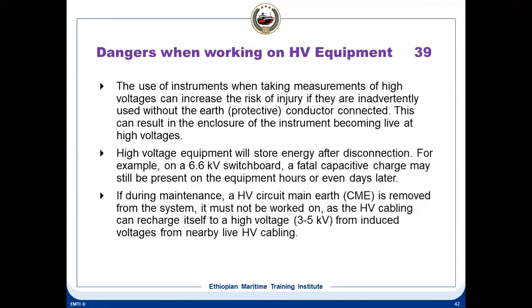The use of instruments when taking measurements of high voltage can increase the risk of injury when they are inadvertently used without an earth conductor. You see, the first thing in a high voltage system is grounding. Everything has to be grounded before you touch anything. The whole purpose of grounding is that any residual voltage has to be discharged to the ground or earth. That's the first part. Whether you use a megger or test the voltage or whatever it may be, grounding is the first part. So this can result in the enclosure of an instrument becoming live at high voltages. Another thing is that the instrument which you are measuring with can increase the risk of injury if it is used without earth.